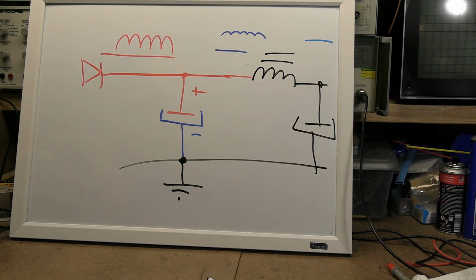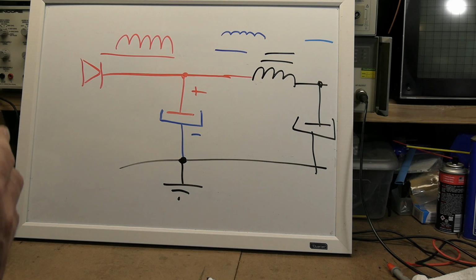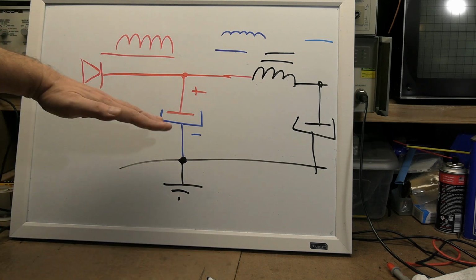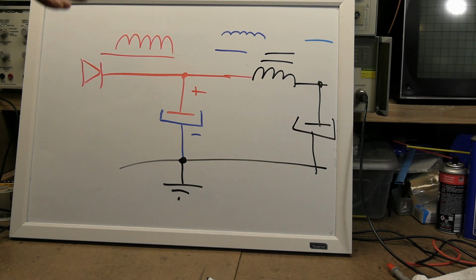At any rate, just like with a lead acid car battery, you have lead and, what is it, lead sulfate, lead oxide or something. There's an insulation layer that builds up on the surface of the metal from a reaction with the acid. It's the same with this, where that electrolyte helps chemically. The aluminum reacts with the electrolyte to build up a compound on the surface that can deteriorate. When we're talking about forming it up, we're trying to invigorate, reactivate that aluminum compound layer that helps the capacitor do its job. That happens by applying voltage to it.